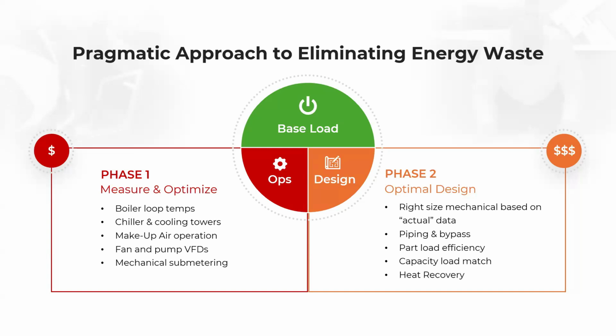So not just measuring, not just relying on the utility bills, or not even just putting in a submeter for all the gas being used by, say, the 3 or 4 boilers in the building, but actually metering each boiler independently in some cases, and the chiller independently, so that the real energy data at the equipment level can be cross compared to the operation of the building and to optimize that design, right?